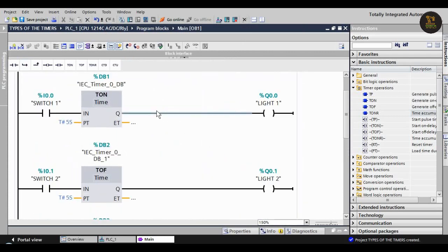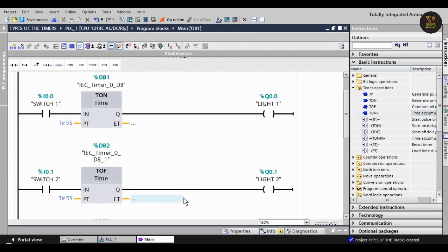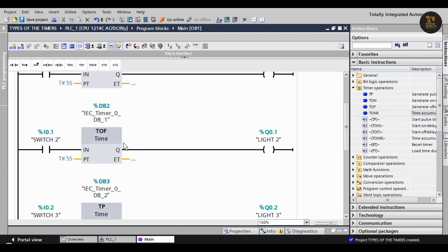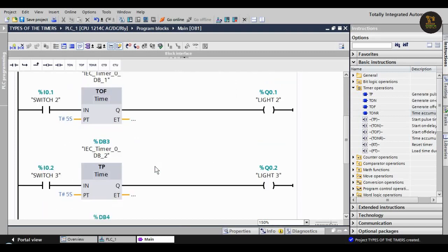Now let's see how all the timers will work. First, T_ON - when we switch on, light will glow after five seconds. In T_OFF, when switch two is on, light two will be on. When we switch off switch two, the light will turn off after five seconds in the off-delay timer.